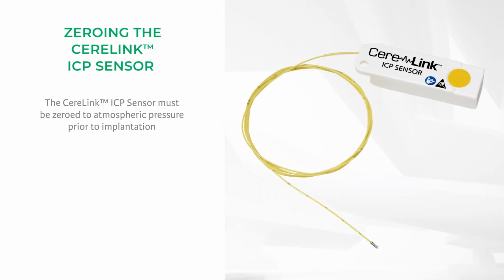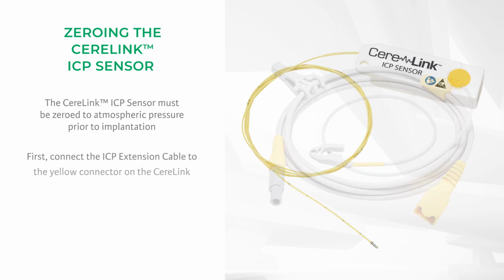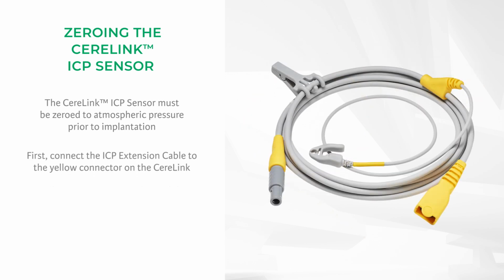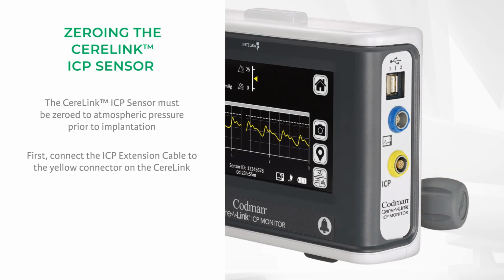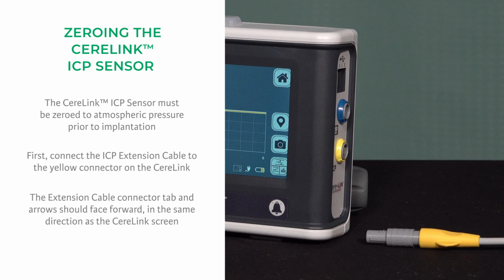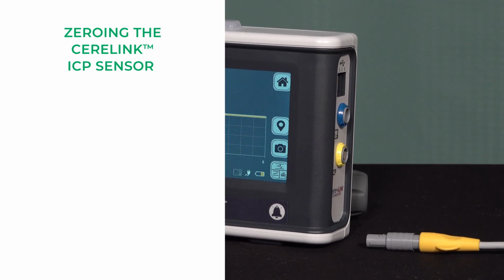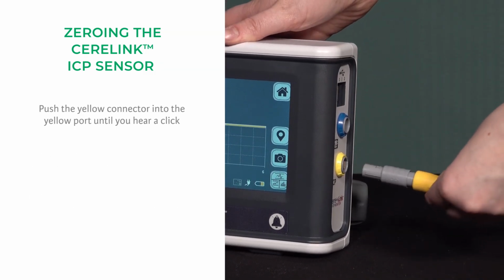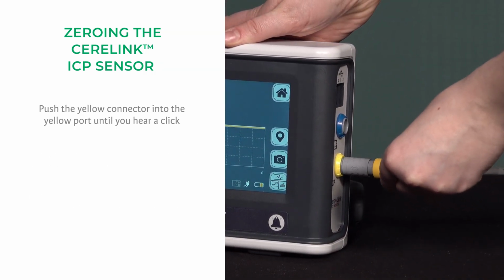The CereLink ICP sensor must be zeroed to atmospheric pressure prior to implantation. First, connect the ICP extension cable to the yellow connector on the CereLink. The extension cable connector tab and arrows should face forward in the same direction as the CereLink screen. Push the yellow connector into the yellow port until you hear a click.